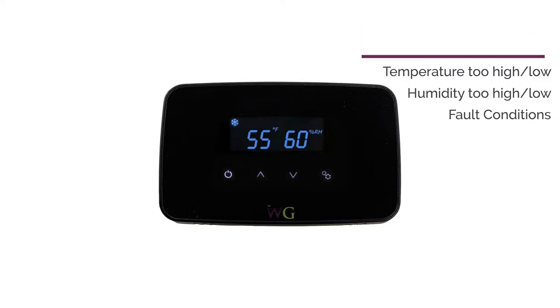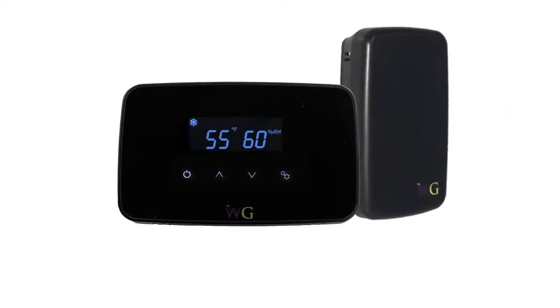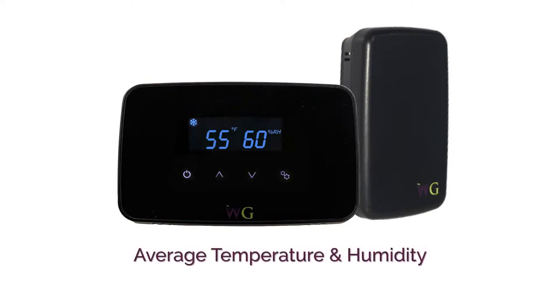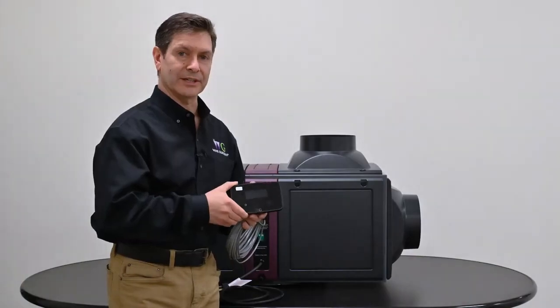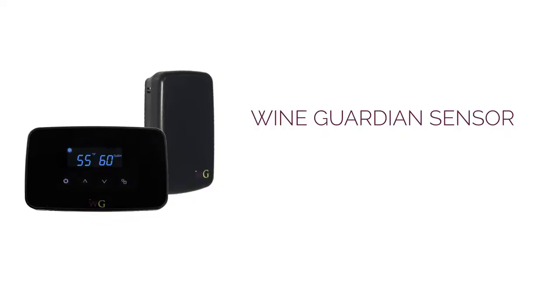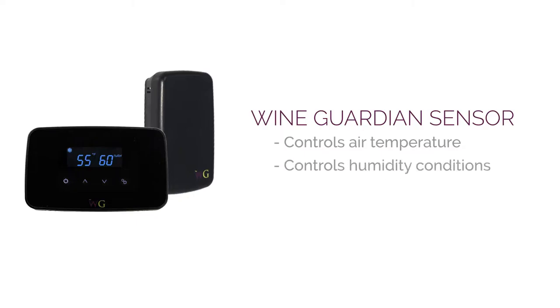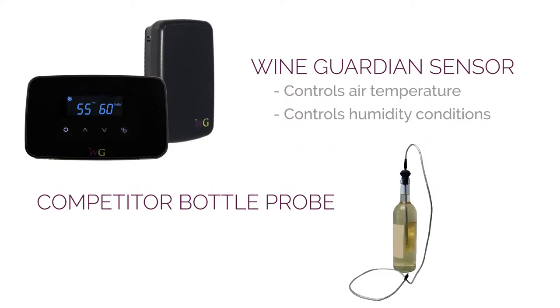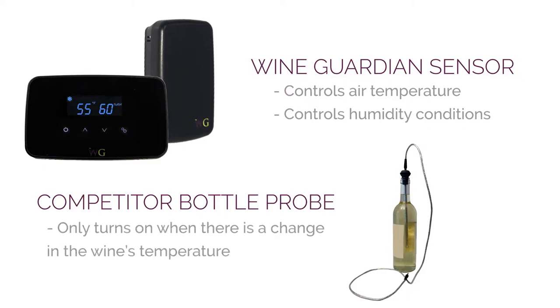Okay. The remote sensors in combination with the controller will provide an average temperature and humidity of the space when they're used together. So this is a key feature when controlling a wine cellar space. We're controlling the air temperature of the wine cellar and the humidity conditions of the wine cellar versus a bottle probe, which is typically connected to a liquid within a bottle, and it only turns on the temperature, humidity, or the wine cellar cooling unit when there's a change in that temperature of the wine or the liquid. That's exactly what you don't want to have happen.